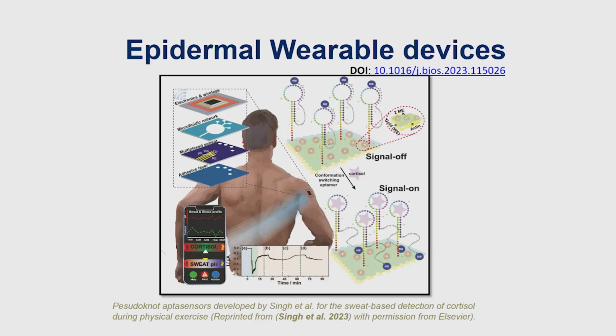That then goes to a microfluidic platform, and your microfluidic platform basically does the distribution of your sample. So you have your sample going in here, and then you can distribute it into different reservoirs, or you can bring in the reservoirs to bring in other reagents. You can do the mixing, and then you can do the measurements. As you can see, the measurement is normally done towards this end here, and underneath that you can see the working electrode, counter electrode and reference electrode, which basically do the electrochemical detection of the devices.